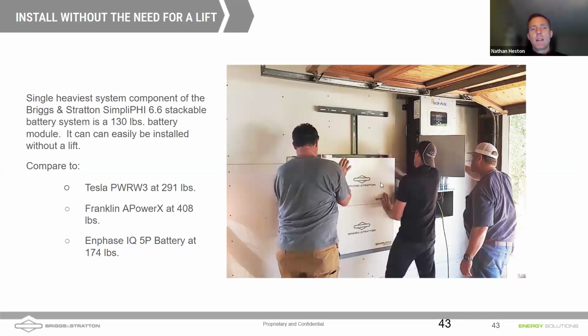These batteries can be fairly easily lifted into place with just two guys. The batteries are about 130 pounds a piece, the modules, and so it's not light, but it's quite reasonable for two installers to put these stacks together. The whole battery system for this install went together in about 30 minutes, so quite quickly. Now there's plenty of time that was spent. We had 18 kilowatts of AC coupled solar coming into this one.